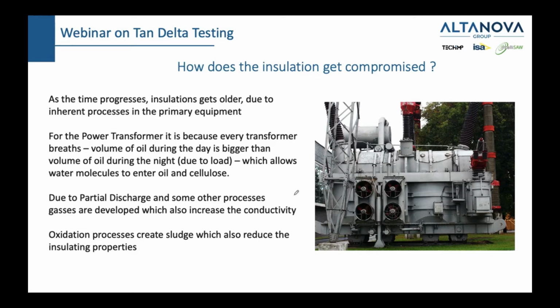The same thing when you breathe. If you want to breathe in, you will expand your lungs, your chest, in order to suck the air inside. And then you will contract it to push it outside. The same is done with the transformer, and that's why a transformer has a breather. The breather is that pipe through which the transformer breathes. At the beginning of that pipe, you have some silica gel, which is put there for a reason, which is to remove all the water molecules from the air. And it does a good job.